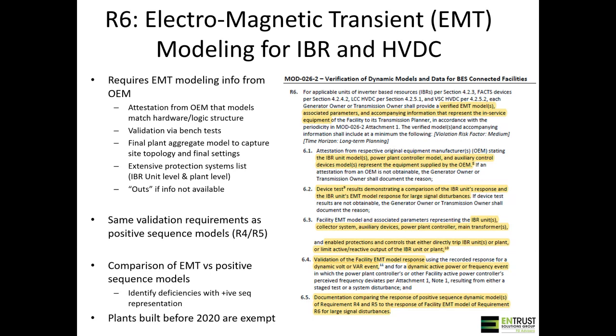So like negative sequence, any type of large disturbance, if a fault happens on a single phase, the way that inverter-based resources behave is not standardized the way that synchronous machines behave. So that's why EMT has become such an important tool, not to mention that the operating speeds of these converters can be down into the microsecond range, which is an order of magnitude different than the concerns we have for synchronous machines. I can definitely present for an hour on why EMT is a necessary tool moving forward in the future. But really what we want to capture here is just that it is now a requirement.